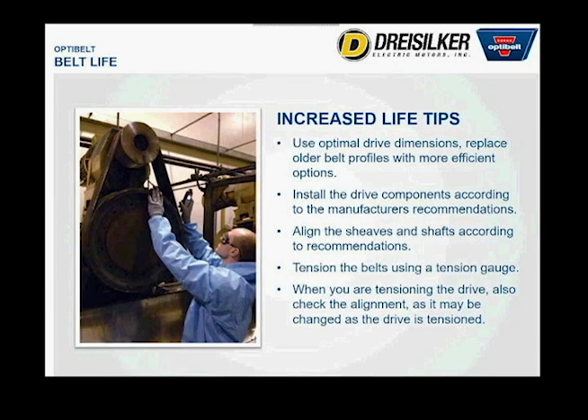Most components come with installation manuals, or at least the taper bushings and pulleys should have something from the manufacturer to tell you how to install correctly. Follow those. When you install or replace your belts, some people use a 2x4, some use a string, we have a fancy laser tool, but try to align the sheaves, because if the belt isn't going in and out of the sheave aligned properly, at an angle, it does more wear and tear and will fail early. And the biggest thing is making sure they're at the correct tension, not too high and not too low.